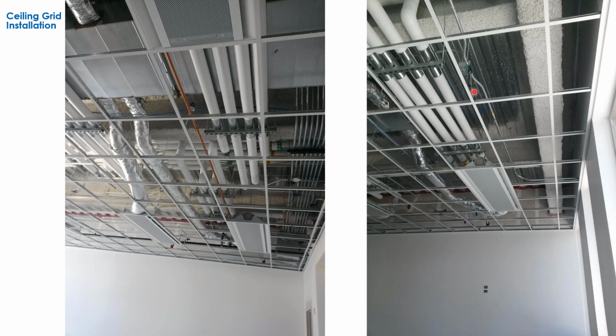Now here are some applications. These are actually 2 different projects where we have 4-pipe chill beams in a ceiling grid. One of the claims of a chill beam system is it needs a very small ceiling plenum because the beams are so small and the ductwork's small, but that doesn't mean it isn't crowded. Look how close the ceiling grid is to these pipes passing underneath the structural steel member here, and you can get an appreciation of how tight this is all going to be. You can see the piping's been insulated and run over. The beam has been lowered down into the ceiling grid. Of course, there's the primary air. It's all been hooked up.